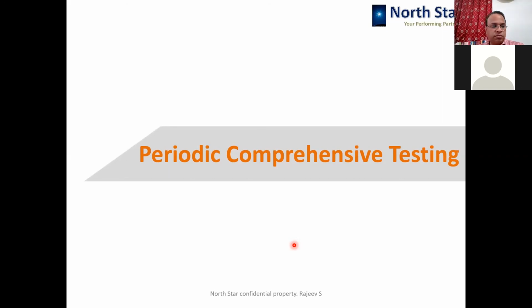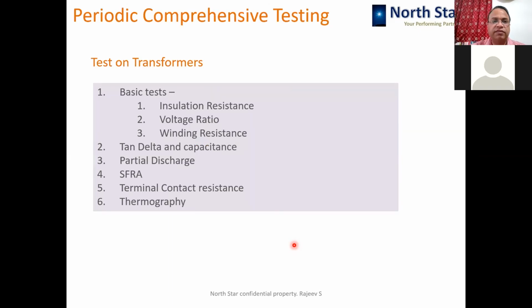of the transformers. So besides that, once in a while, depending upon the criticality and the transformer size, we should do some detailed testing of the transformer so that we are comfortable and at peace that everything is right with the transformer. So other than basic tests like insulation, voltage ratio, winding resistance, tan delta and capacitance, partial discharge, frequency response analysis, terminal contact resistance, and thermography. These tests are recommended to be done on the transformer, and oil tests, which we have talked about, Furan and DGA, those two tests must also be done. DGA is a little bit more frequent compared to Furan.